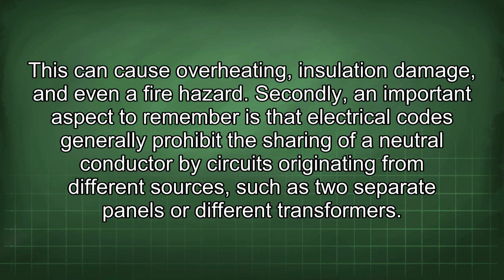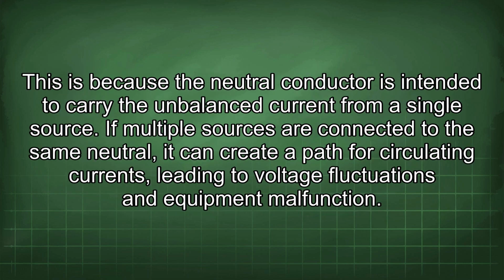Secondly, an important aspect to remember is that electrical codes generally prohibit the sharing of a neutral conductor by circuits originating from different sources, such as two separate panels or different transformers. This is because the neutral conductor is intended to carry the unbalanced current from a single source.